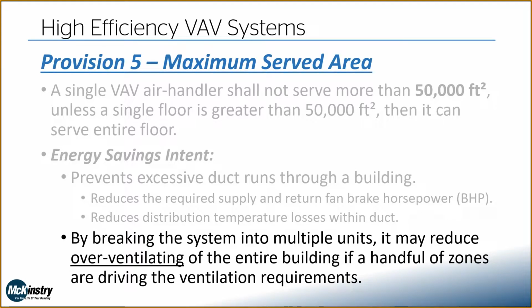Additionally, if we can break that system into multiple units, we can prevent over-ventilating the entire building. So if you have one or two conference rooms that are driving the ventilation requirements, if we have more units, there's less chance that that's going to over-ventilate the entire building. It may over-ventilate one section of it a bit, but it will limit that from happening.